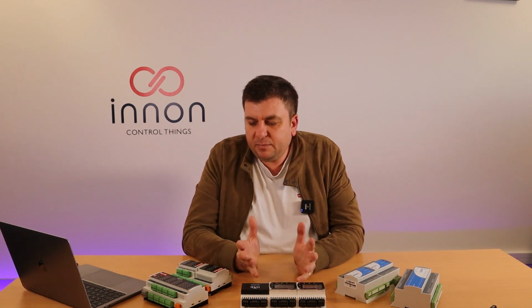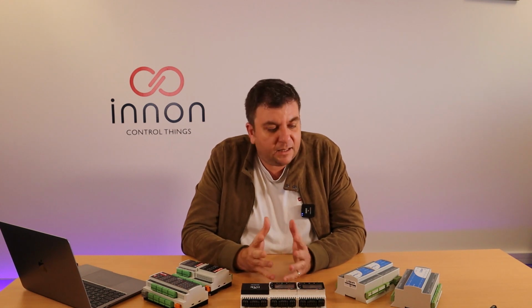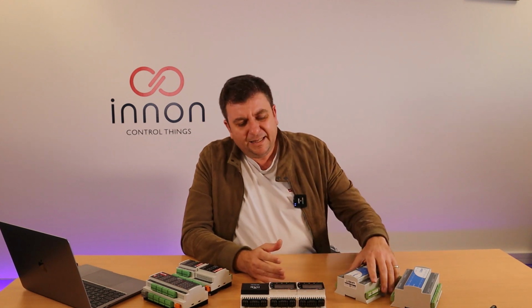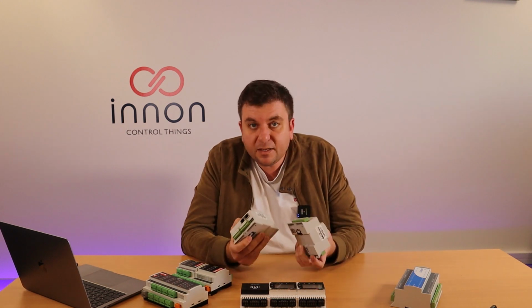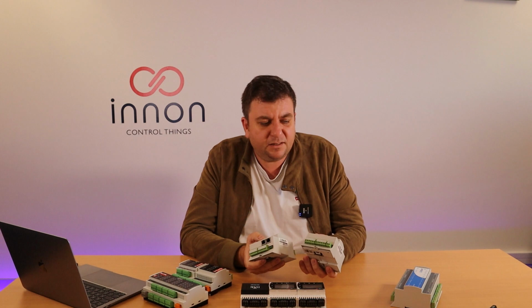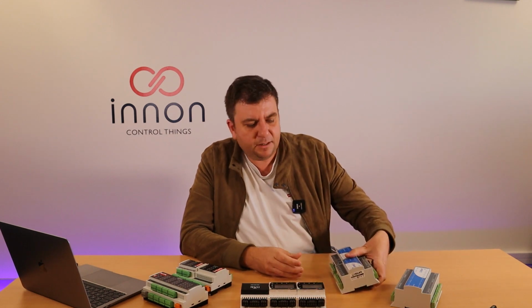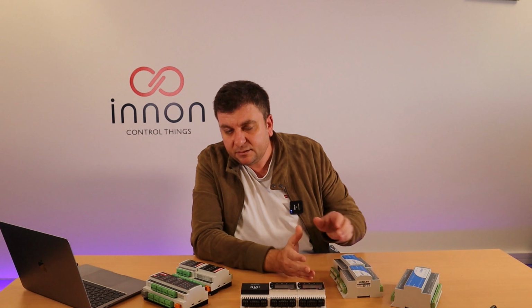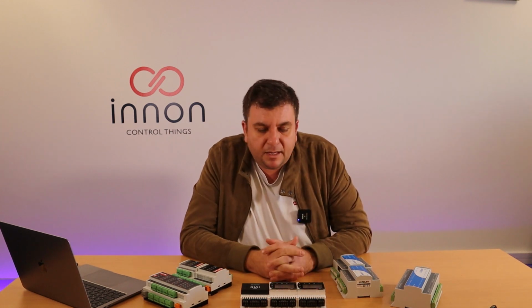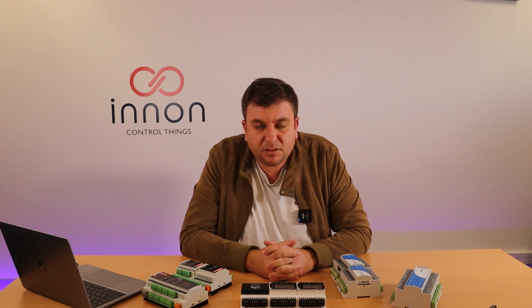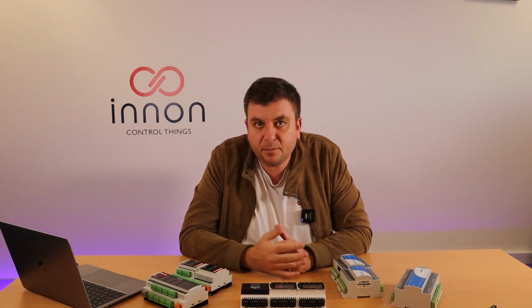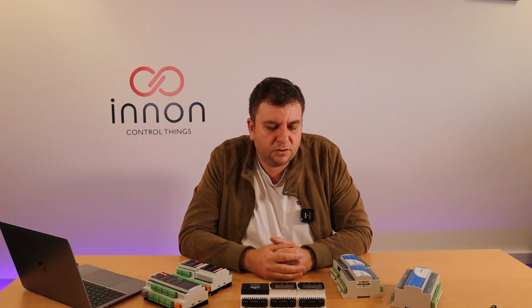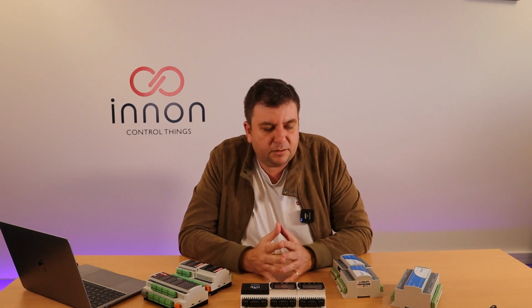And I'll go into a bit more detail. So you will notice that Open Protocol I/O modules are IP and RS-485, and that's a feature across pretty much every manufacturer nowadays. Why would you need one or the other? Well, it depends on the building. If it's an old building, perhaps it's difficult to run a cable. Newer buildings tend to have IP infrastructure, so that's handier. Depends on the specification of the consultant and so on. So straight off from the beginning, you will find them in either IP or RS-485.